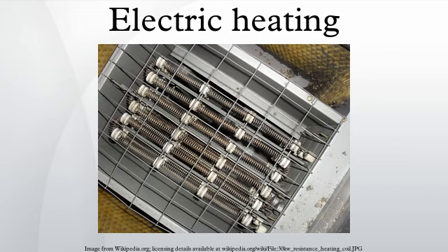Economically, electric heat can be compared to other sources of home heating by multiplying the local cost per kilowatt-hour for electricity by the number of kilowatts the heater uses. For example, a 1500-watt heater at 12 cents per kilowatt-hour: 1.5 x 12 equals 18 cents per hour. When comparing to burning fuel it may be useful to convert kilowatts to BTUs.